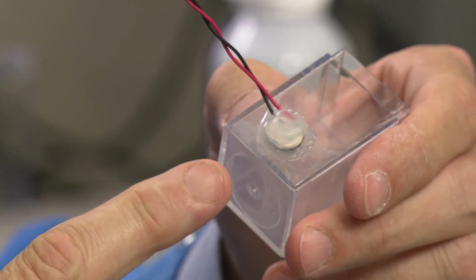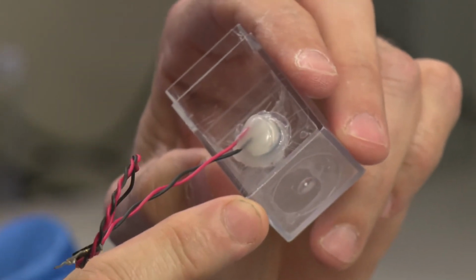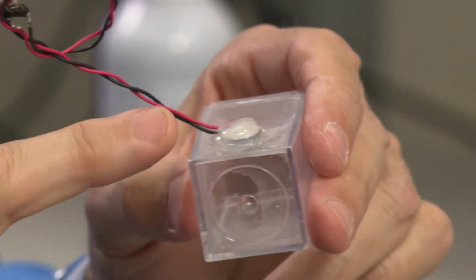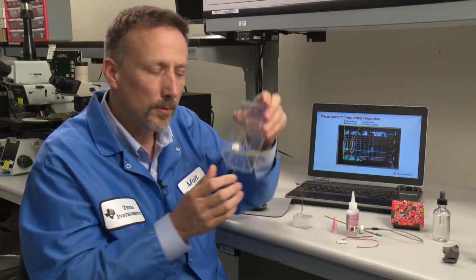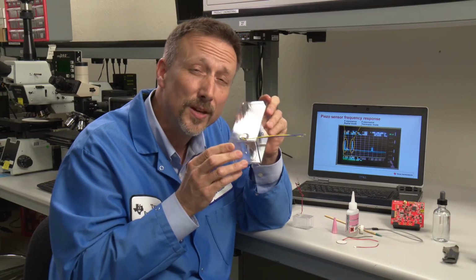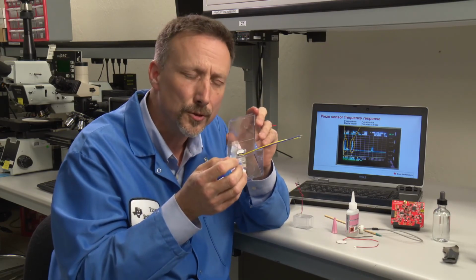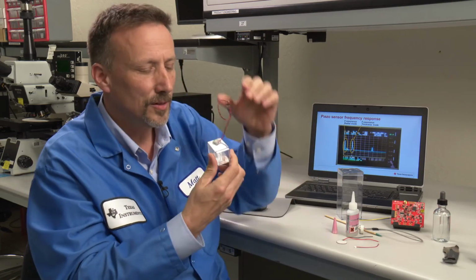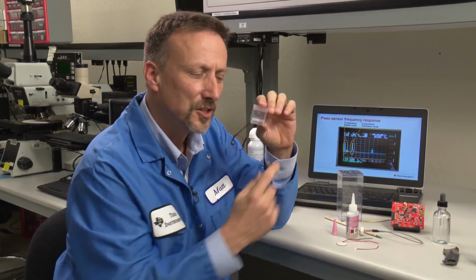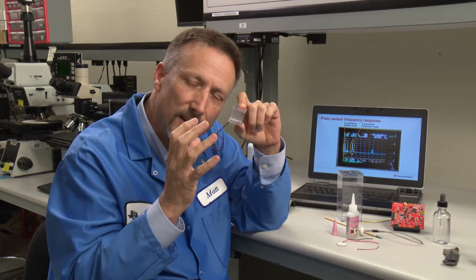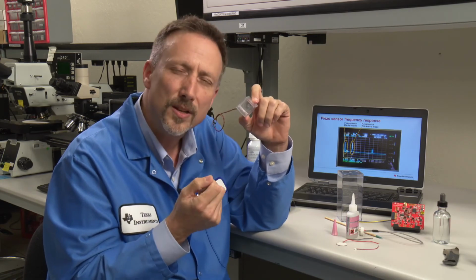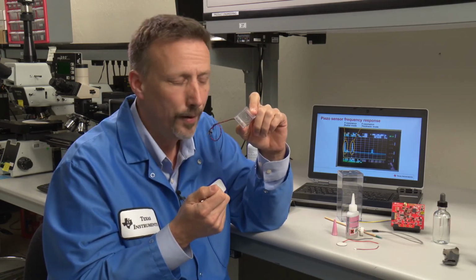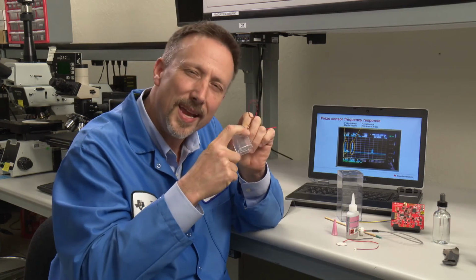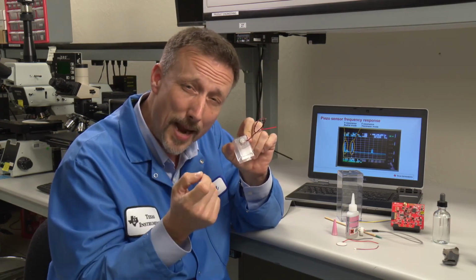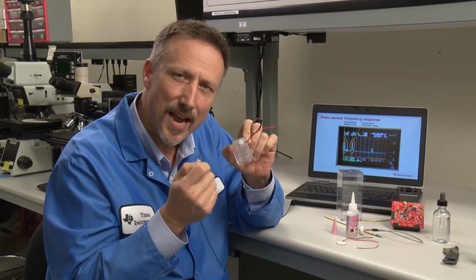Some other things you can do, depending on how good your transducer is, include acoustic dampening on the back of the transducer. For this example, I didn't need to because this transducer is very efficient and larger. In the case of trying to detect a signal very close to the transducer, every transducer, when excited, rings. This is called ring down in your transducer specification. By applying an absorptive adhesive to the back of the transducer, I can minimize that ring down.